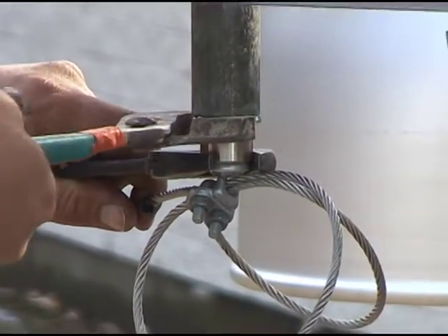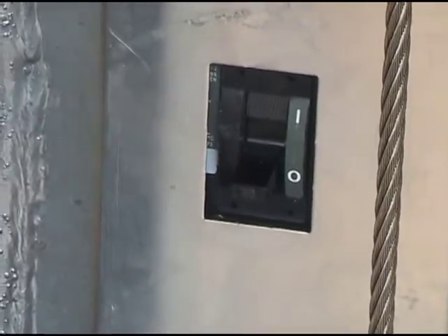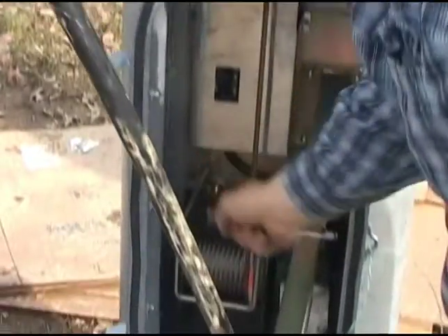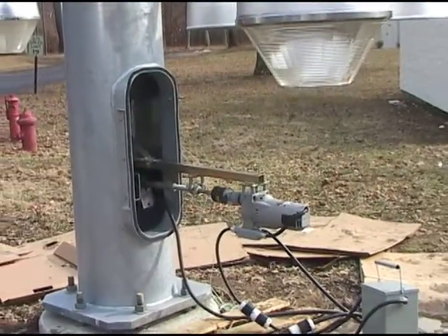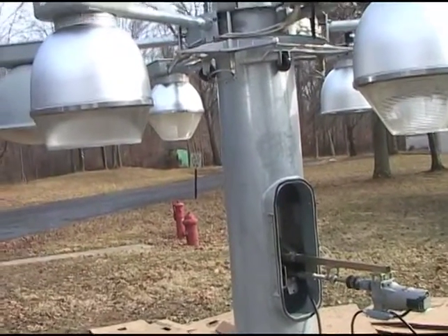With the device in the lowered position, the lights can now be tested by disconnecting power, plugging the pigtail into the receptacle on the junction box, and re-energizing the device. If all the lights are functional, the device is now ready for testing of the latch and unlatching sequences.